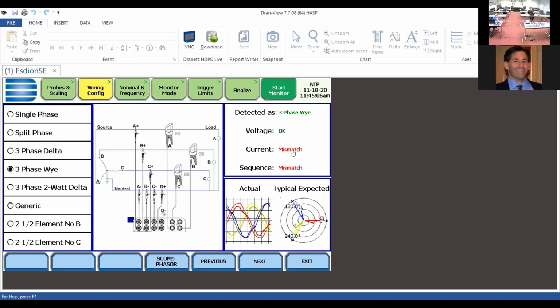So when that happens, your currents aren't going to be in the ideal range to give you the best accuracy. The instrument will come back and tell you that you have a mismatch. These two work hand in hand. If I'm under current as far as whatever current probe I'm using, and I have a mismatch, then I'm not going to be able to determine the sequence. We get those calls quite commonly, and usually it's a matter of the current probe being under range.